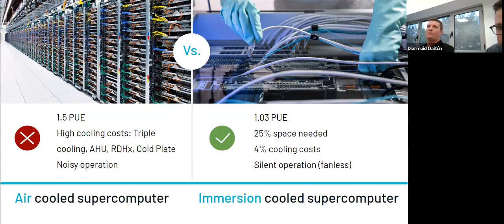Now, we've done a little bit of a trick here with the PUE, because the reported PUE of Summit is between 1.15 and 1.2. Yeah, exactly. But of course, we need to account for the fans that are in those systems and that obviously immersion environments don't have. So this is what we're typically seeing in air-cooled supercomputers as a kind of medium PUE.